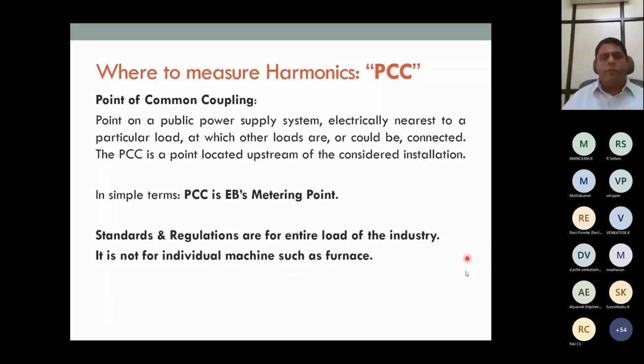Do we have to measure harmonics in the machines we use, like a furnace or a spinning frame or a motor? No, we have to measure harmonics only at the PCC. PCC is called the point of common coupling. For an industry, the PCC is exactly the metering point or near the metering point. So all the regulations and standards are for the PCC and not for the equipment used. This has to be very clearly understood.